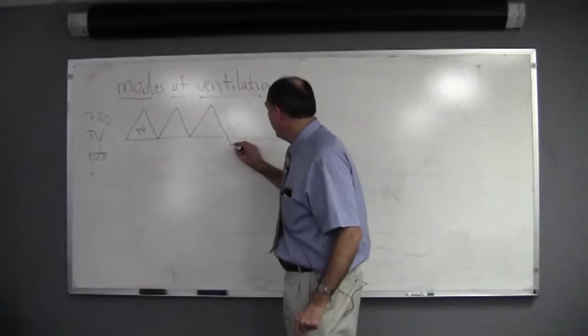But if the patient should take their own breath, what we want the machine to do is sense the negative pressure, because that's what the patient creates, right? That little negative pressure, and then it resets itself and gives another breath. So it would allow the patient to initiate their own breath, but at the same time reset itself, so there's less bucking, okay? There's more synchronization with the patient as they wake up, as they become more conscious, as they take more spontaneous breaths.